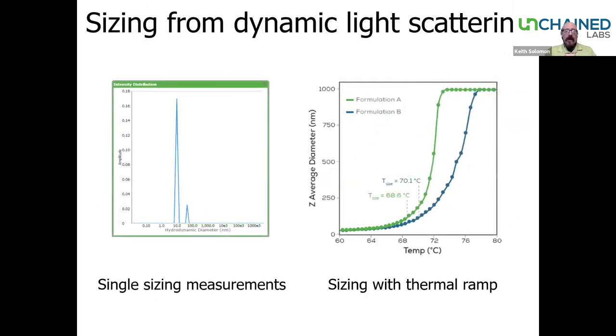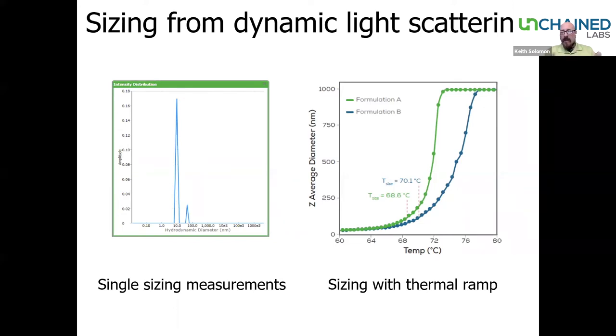UNCLE also does really nice dynamic light scattering. On the left you can see a single DLS measurement of an antibody showing the expected hydrodynamic diameter of around 10 nanometers and a slightly larger peak of some aggregates. On the right, you can see DLS as a function of temperature for two different formulations of a protein, capturing the change in hydrodynamic diameter as a function of both temperature and formulation using the UNCLE instrument.